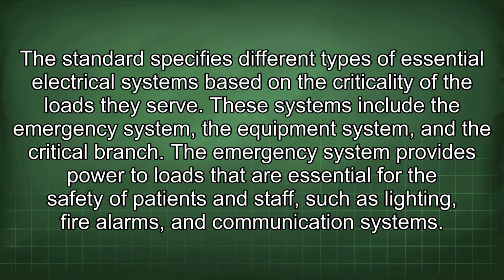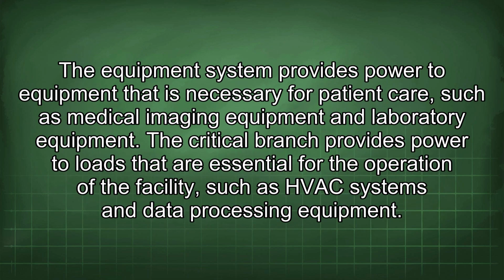The standard specifies different types of essential electrical systems based on the criticality of the loads they serve. These systems include the emergency system, the equipment system, and the critical branch. The emergency system provides power to loads that are essential for the safety of patients and staff, such as lighting, fire alarms, and communication systems. The equipment system provides power to equipment that is necessary for patient care, such as medical imaging equipment and laboratory equipment. The critical branch provides power to loads that are essential for the operation of the facility, such as HVAC systems and data processing equipment.